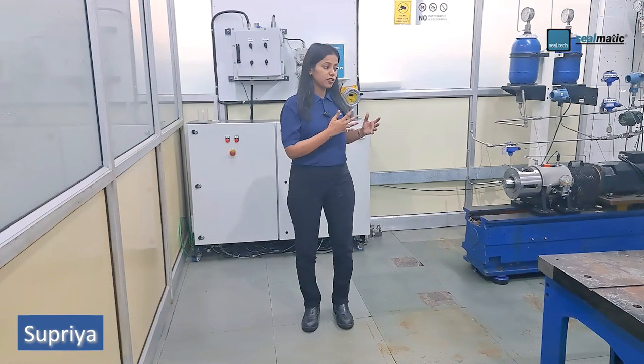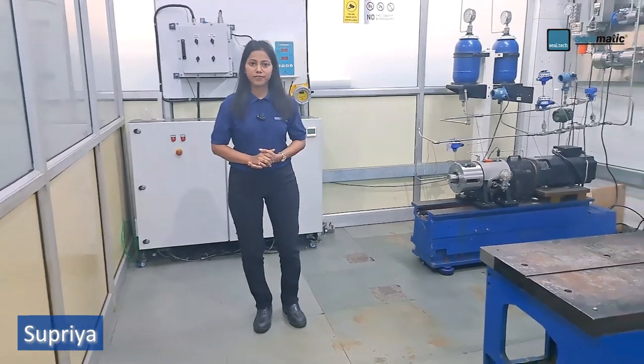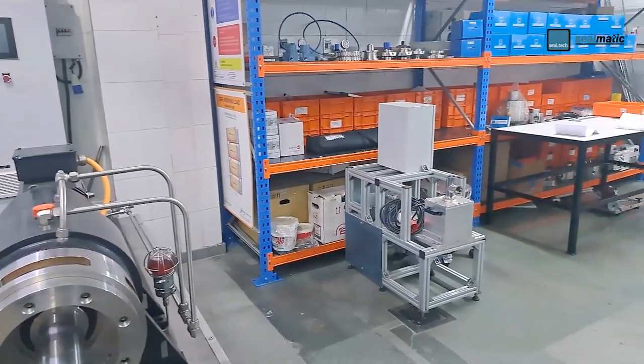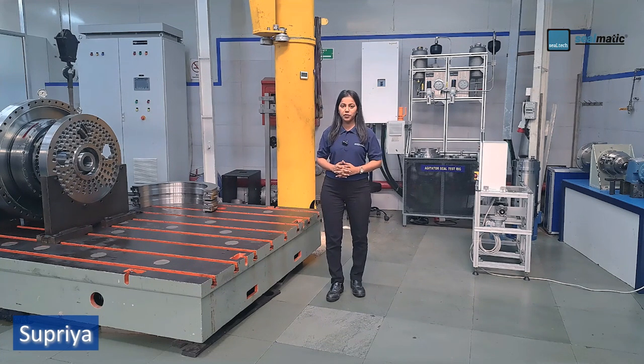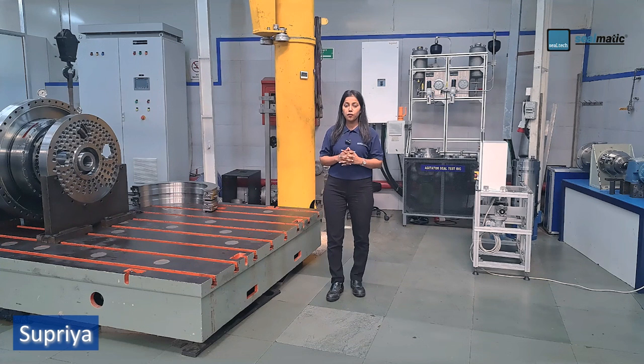So, what are the types of tests offered by Sealmatic? On our test rigs we simulate different conditions and test all types of dynamic seals with a variety of medias. We have installed test rigs which can test as per API 682 for speeds up to 25,000 rpm for ultra vacuum seals, as well as high pressure up to 150 bar for mechanical seals of shaft sizes up to 600 mm, and which can test API seals, gas seals, boiler feed seals, pipeline seals, as well as cartridge seals.